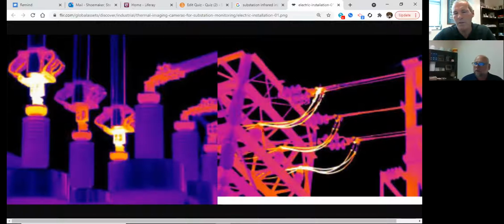On the other bushing of the transformer, you'll notice some conductor jumpers going from one side to the other. I can tell you right here what the problem is: these conductor sizes are probably too small. This conductor size is big, allowing more amperage to flow, but these are too small, and obviously they're going to heat up.